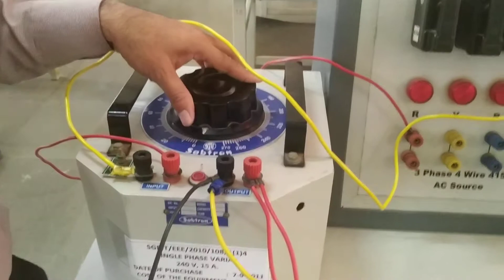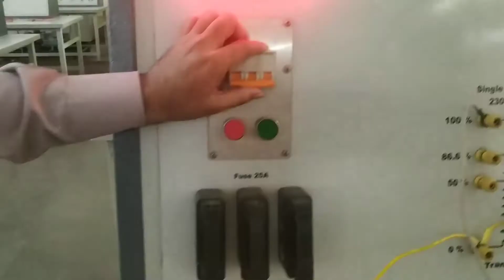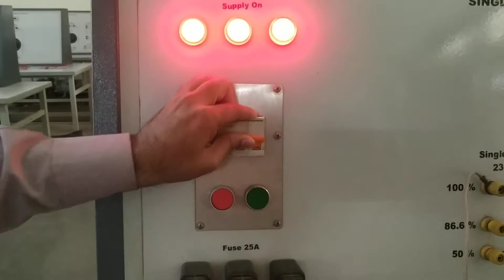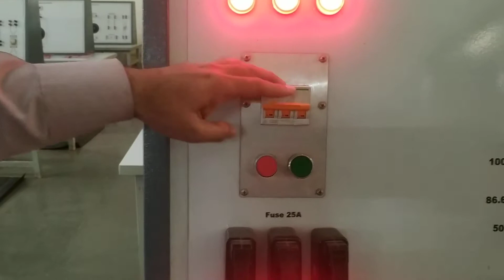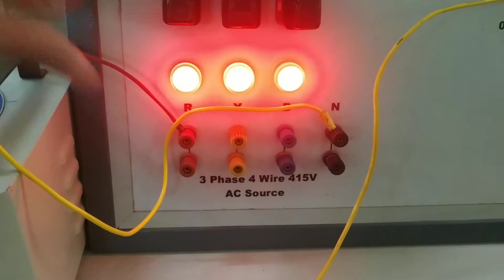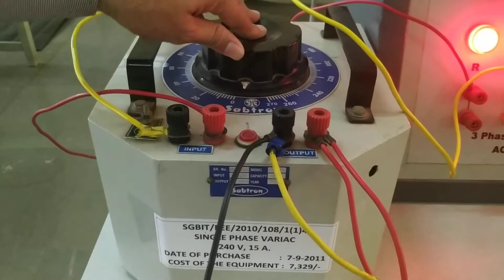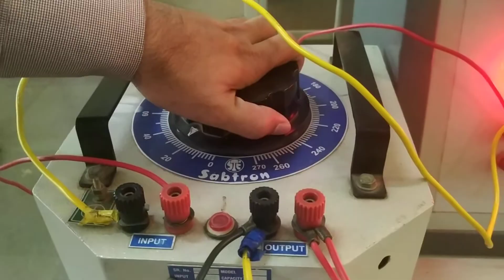First we need to check whether the position of the auto transformer is at 0 or not. Now it is at 0, so we can switch on the main supply by using this MCB as well as the push button. Now the supply is available in these terminals, and from this we give the supply to the input of the auto transformer. Now we can apply the rated voltage to the primary circuit of the transformer during the OC test. With the help of the auto transformer we can increase the voltage, and at the same time we need to observe the voltmeter to see whether the voltage is changing. Slowly we apply the voltage to the primary circuit.